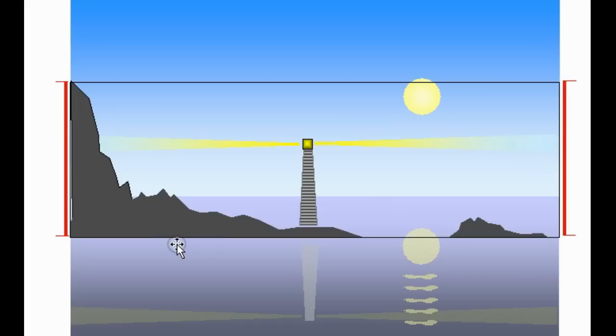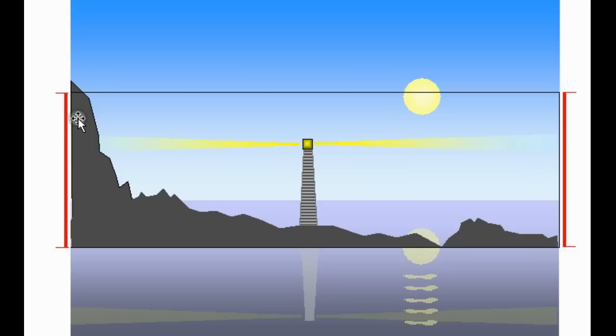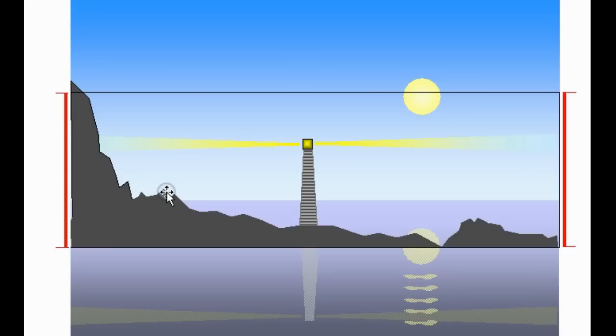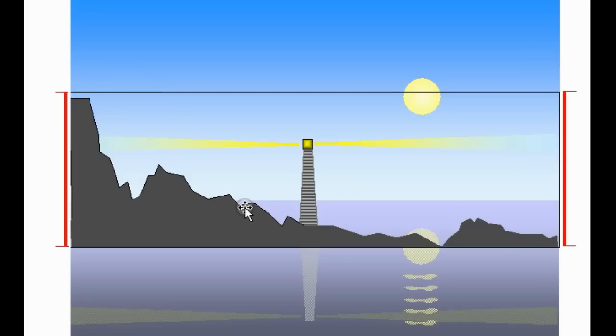Going back to the ocean view, we can continue to reduce the attenuation, making our analyzer more sensitive. But here we run into a problem. Because now, this high energy signal at the left hand side has exceeded the dynamic range of the analyzer. The analyzer cannot plot this information, so it gets distributed to other parts of the spectrum, producing a false result.